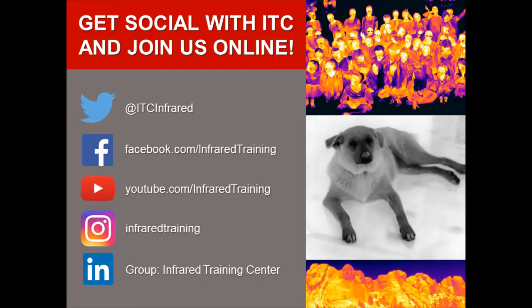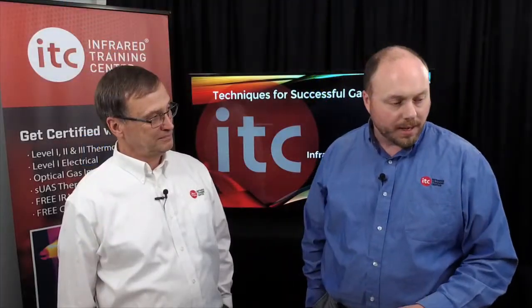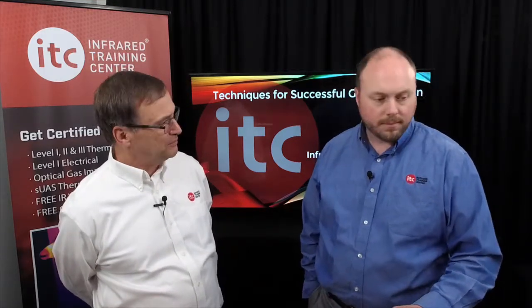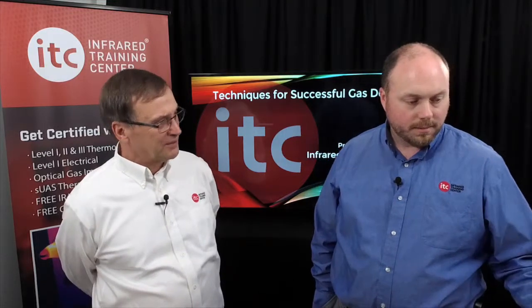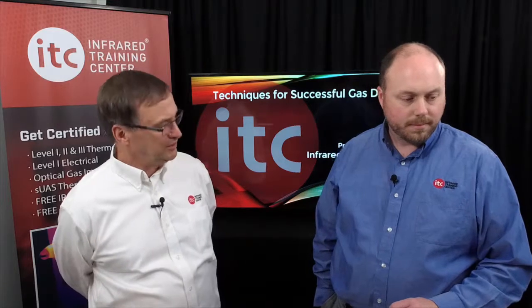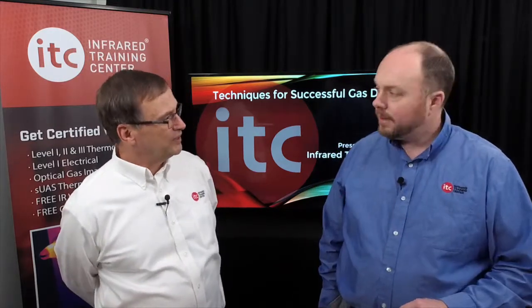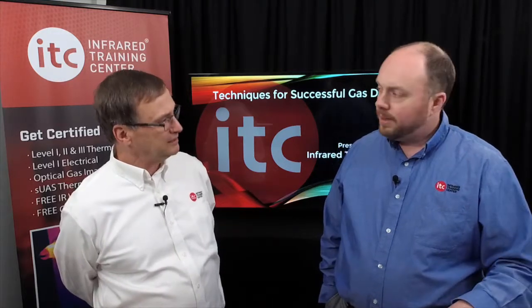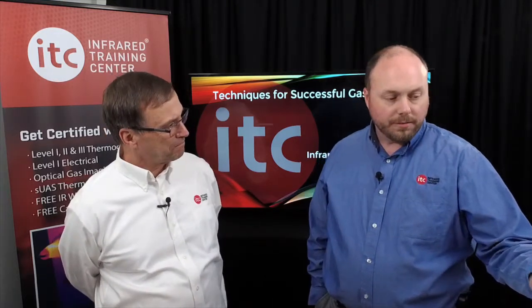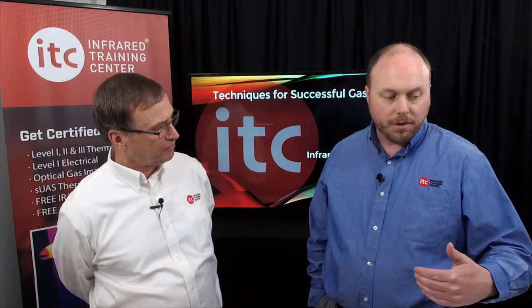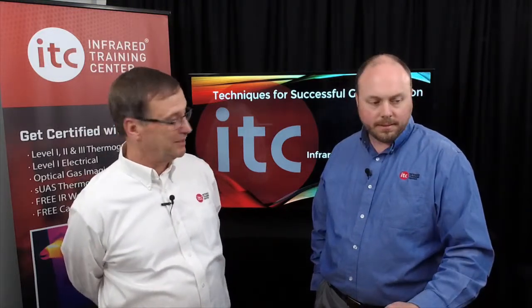From John, is there such a thing as a website or video that identifies different gas volumes that one can use as a reference when using the camera? I'm not sure. The EPA standard that we certify the cameras to is a 50-50 mixture of methane and propane at 10,000 ppm, which is 1% diluted. The standard says you can use any gas that you can see that is more than 98% concentration. So butane or propane is a good use. I think he was getting at possibly using video to compare versus a known set of volumes. Oh, gotcha. We don't have anything like that. That'd be a great paper at some point.